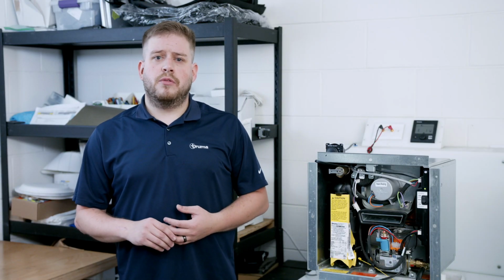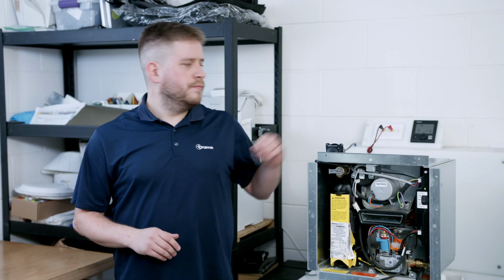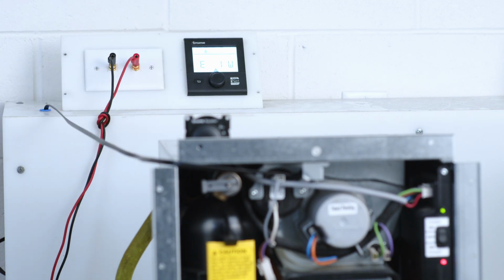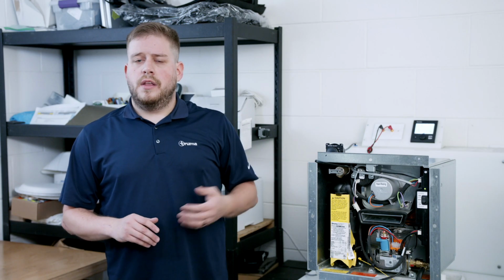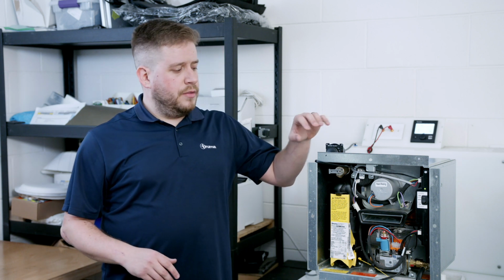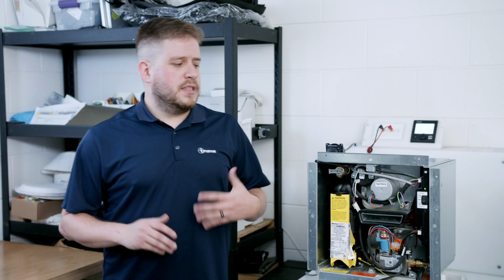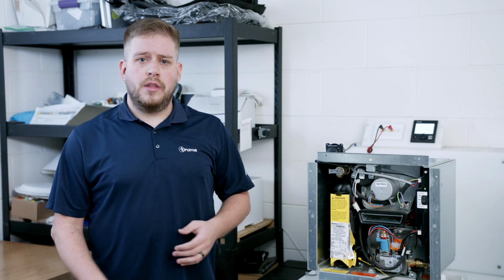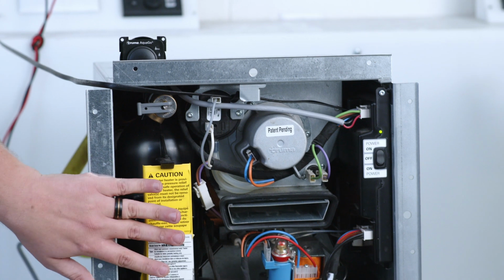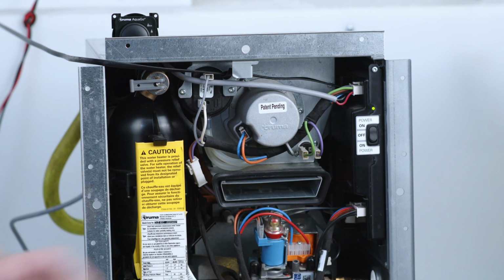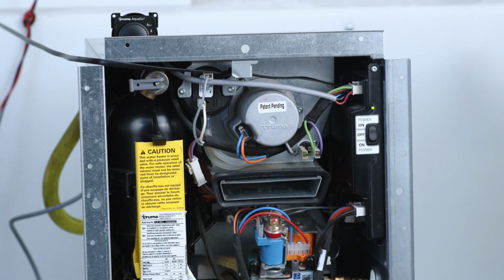Now, depending on the type of control you have for your water heater, the error codes are going to be displayed in different ways. If you have the CP Plus control system, the error code will be generated and displayed on the screen. If you have the dial control, the error code will be generated on the physical dial telling you there is an error code. It can't tell you what specific one it is, but there is an error code. To see what specific error code you're dealing with, you'll go to the outside of the unit, open the door, and read the flash code on the physical control board.